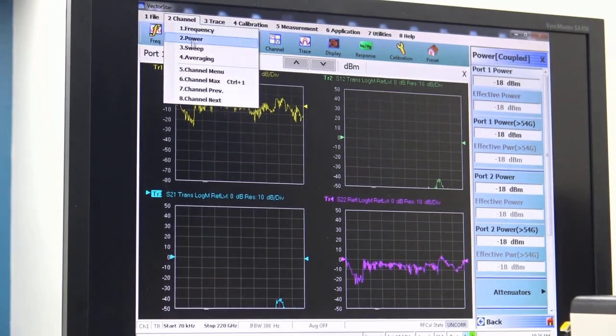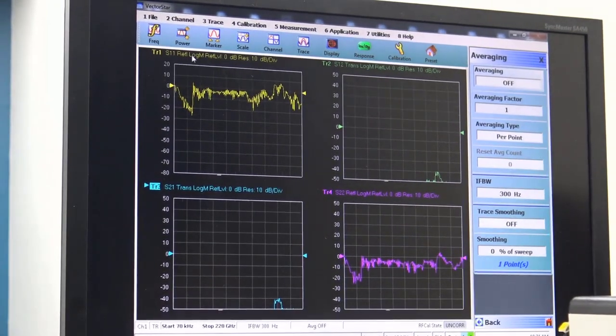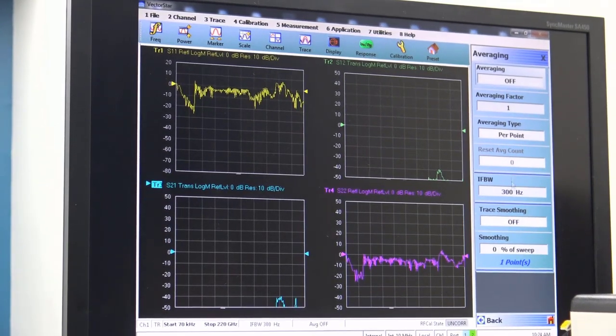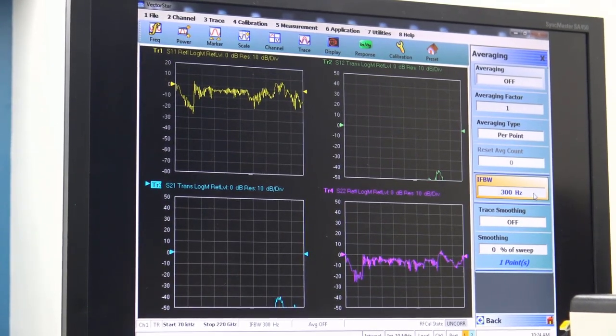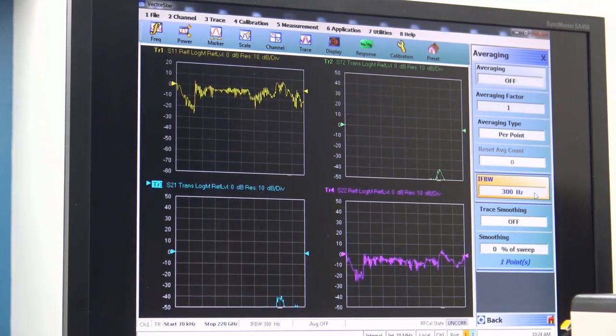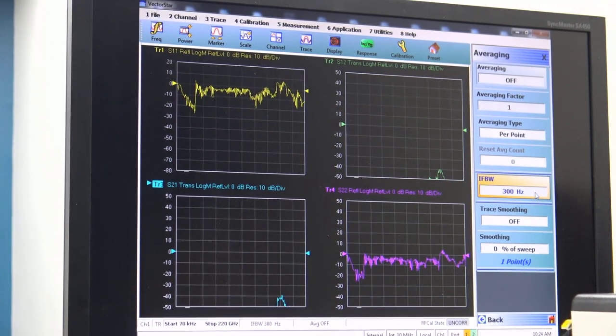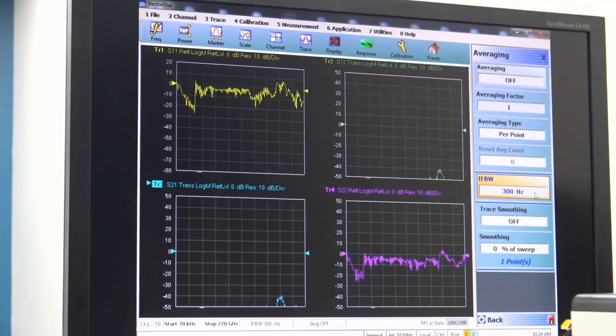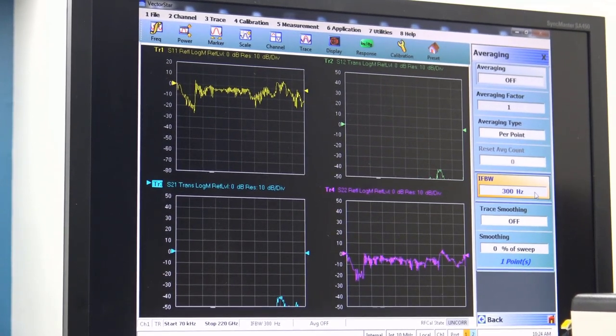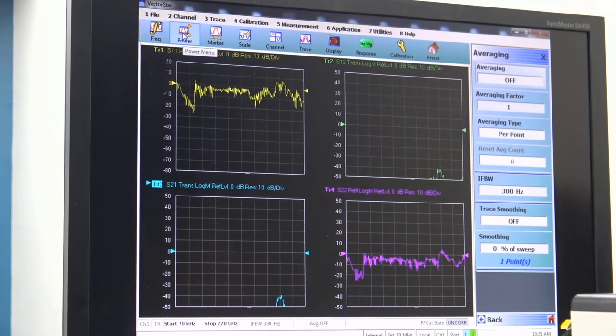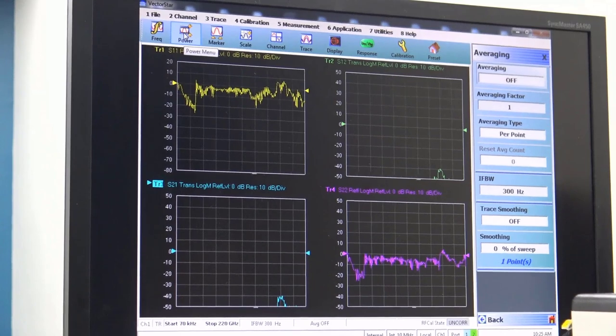Then the final thing we'd want to do is go to our channel menu, select averaging, and verify the IF bandwidth is about where we would want it to be. In this case, I have it set for 300 Hz. You can set it for whatever bandwidth that you want depending on how low of a power level and the dynamic range that you're looking for. So that sets up our frequency, power, and averaging.